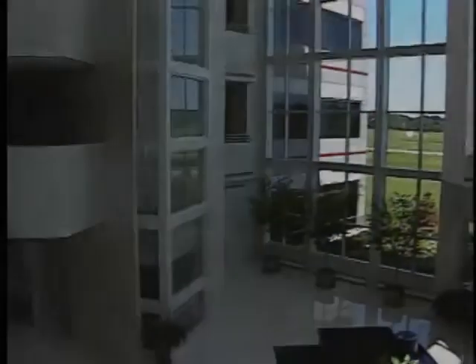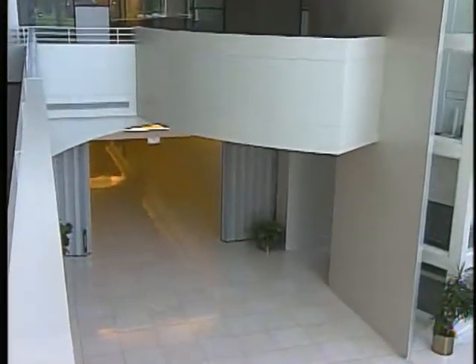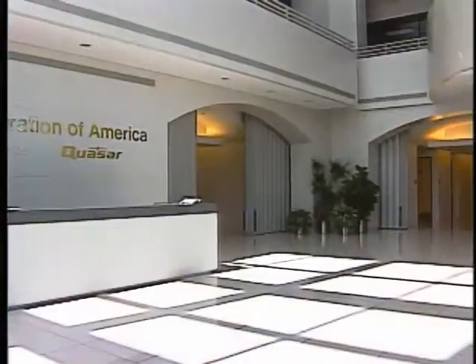smoke, and even heat. The addition of continuous blankets of fire protective liner within the interior cavity of the 2 walls and flexible gasketed perimeter seals for smoke control allows the doors to be fire rated for up to 3 full hours. The door can also bear an S-label as a smoke control assembly where required.